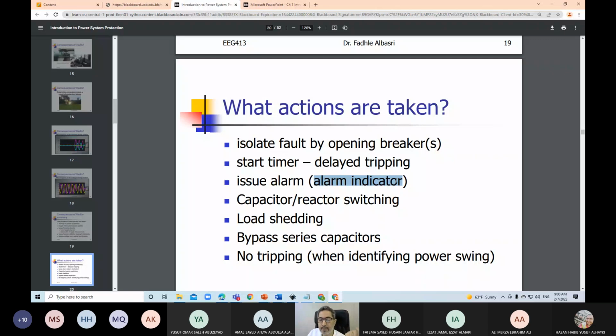Sometimes a relay switches on a capacitor or a reactor to regulate a voltage. Okay, but in that situation, the relay is not a protective relay. We call it a regulating relay. Or sometimes we disconnect load, and these are load shedding relays. Okay.